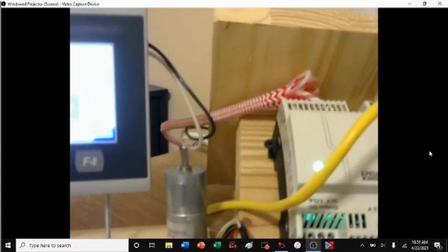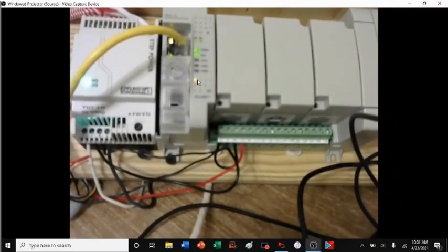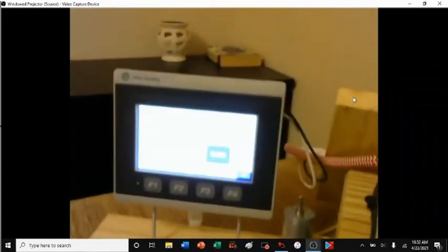And it does, right? There's 2 seconds, there's 5 seconds, 6 seconds, the motor comes on, okay, and then of course your address on the PLC, address 0, output 0 is on in that position. And then of course I could also stop it from here. If I hit my button, it stops, resets to 0, and then my motor indicator goes off. Okay, I'll go ahead and reset my camera.